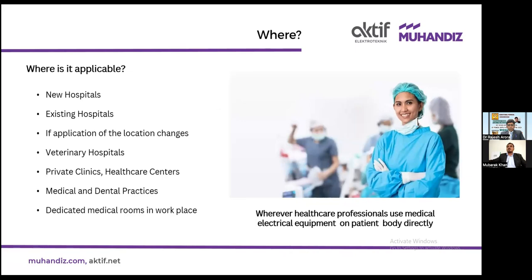Okay. Just to summarize, wherever healthcare professionals use medical electrical equipment on a patient's body directly, these standards must be applied. One more point to mention is that, as it is mentioned, if applicable, the application of the location changes. What it means is that in medical terminology, medical locations are divided into 3 zones: Group 0, Group 1, Group 2. And for each zone, the safety provisions required are different. So if the application changes from Group 1 to Group 2, definitely the safety provisions need to be checked whether it is complying with Group 2 or not.